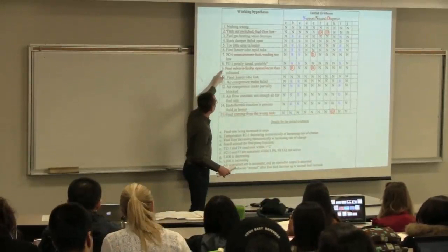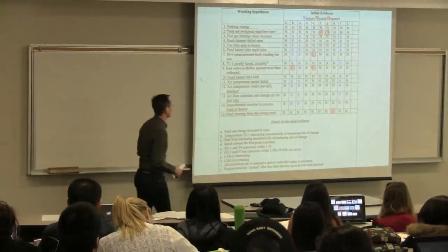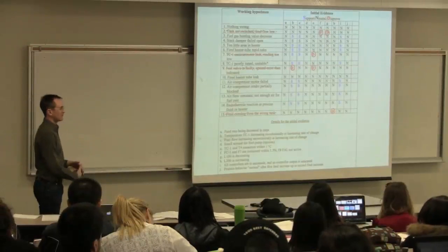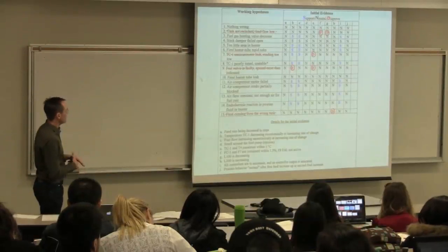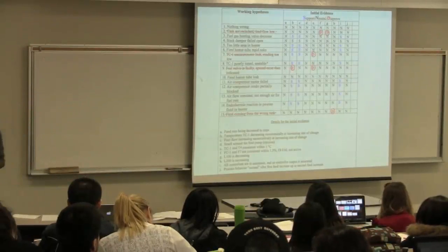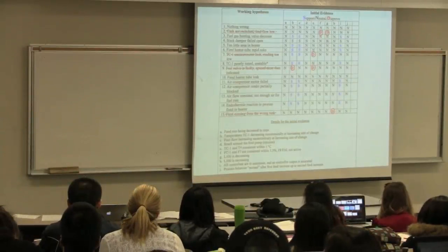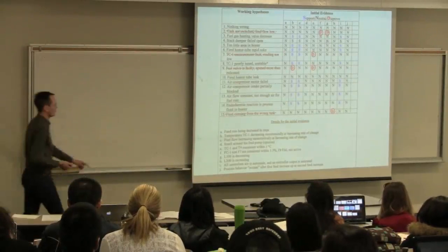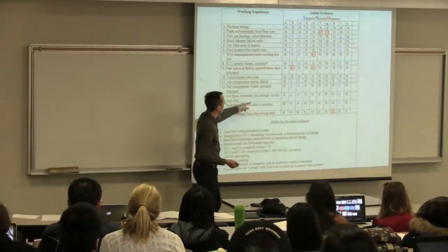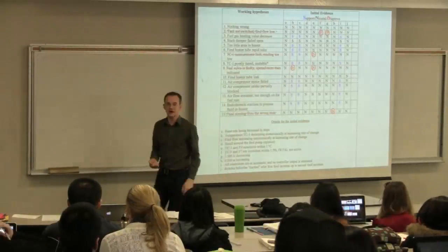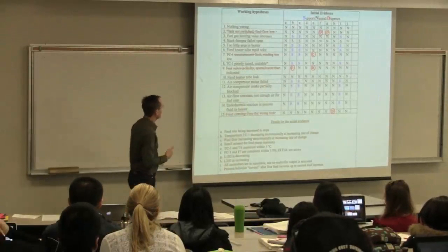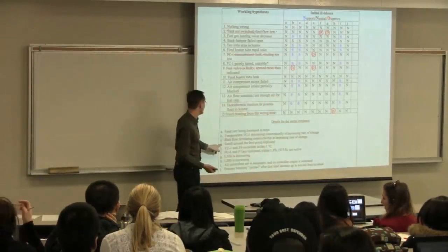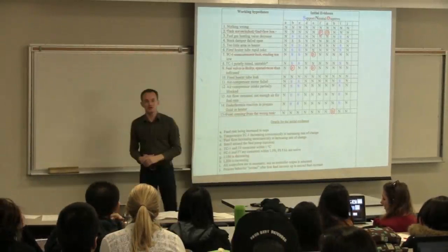Let's take a look then at number 9. The fuel valve is faulty and opened more than indicated. Well, if the fuel valve was faulty, that was the initial hypothesis there, I would expect, and if it was open more than indicated, it's essentially feeding more fuel. If everything else is okay, I should be burning that fuel, and temperature 1 should be going up. So TC1 decreasing monotonically does not support that hypothesis at all. So I can rule that out. That eliminates hypothesis number 9 from consideration. I've got a piece of evidence down here that disproves that could be the cause.